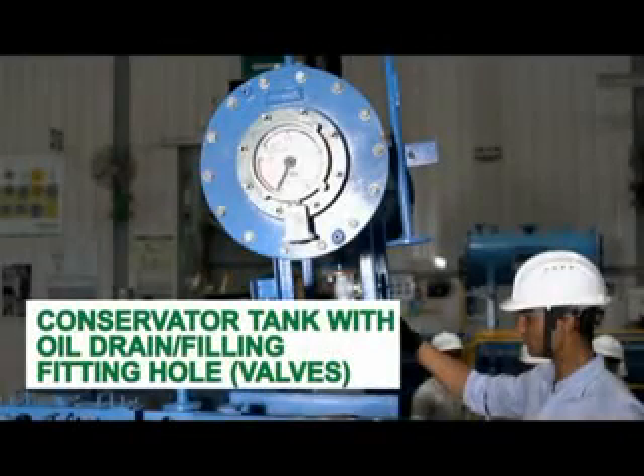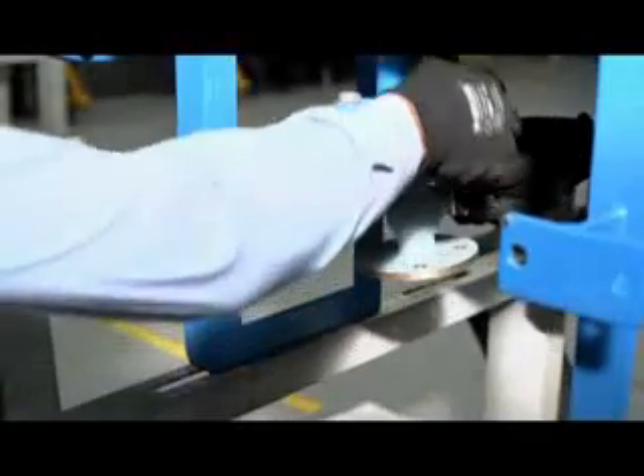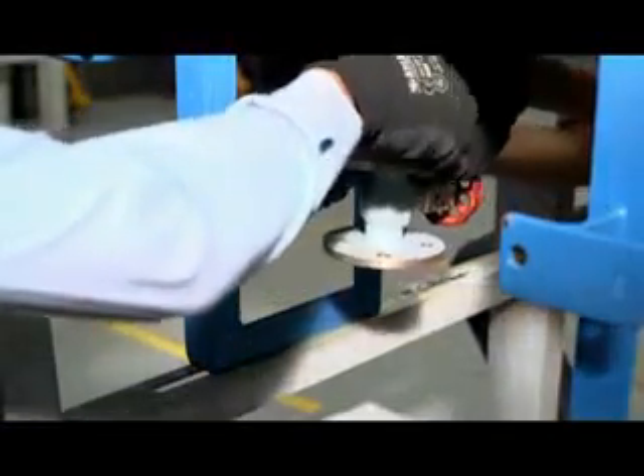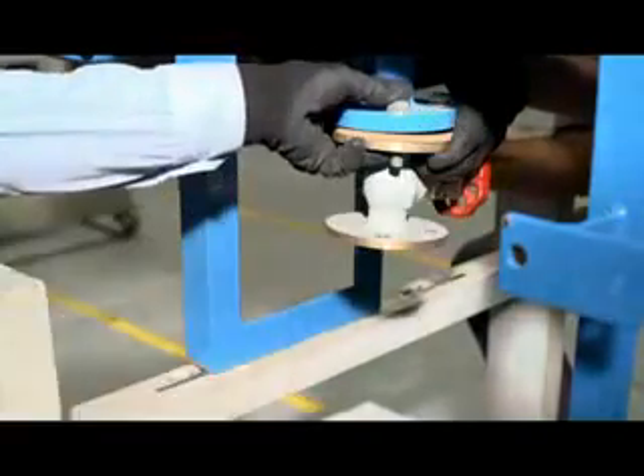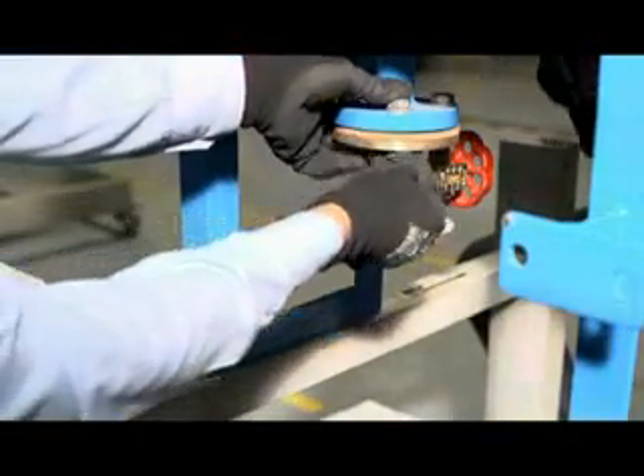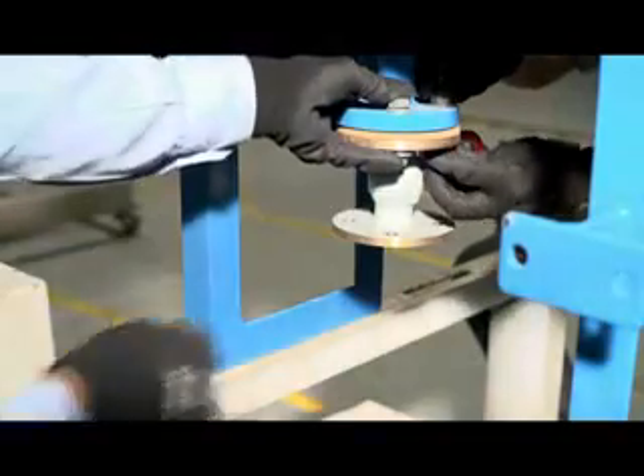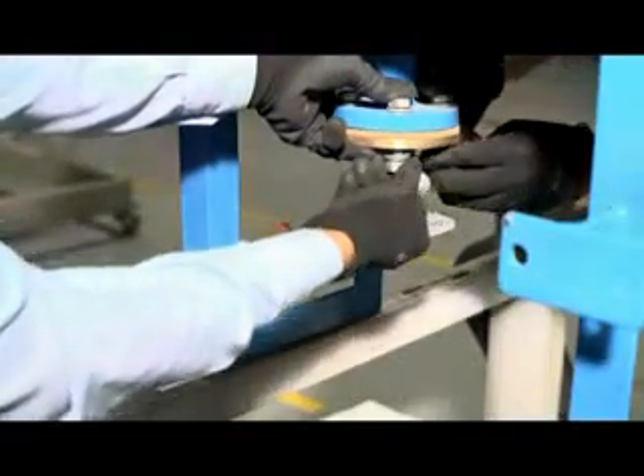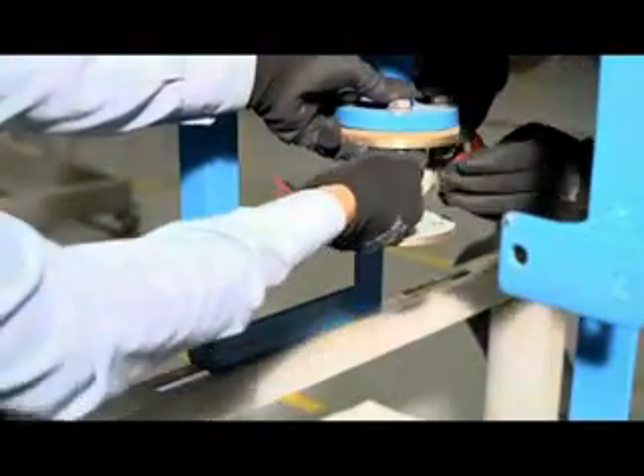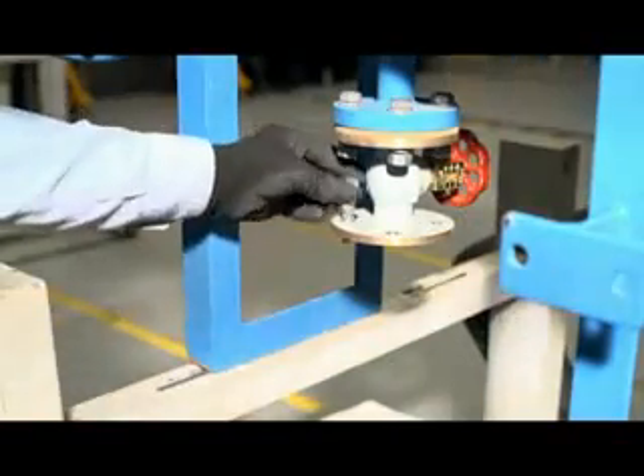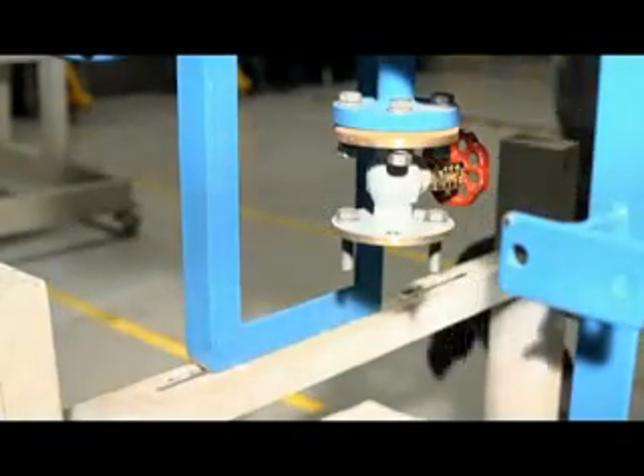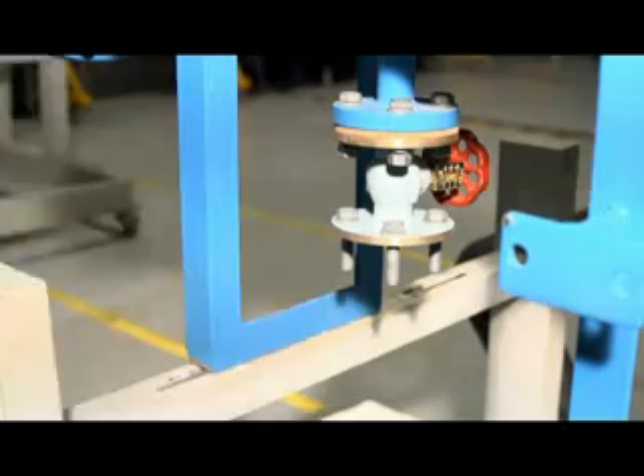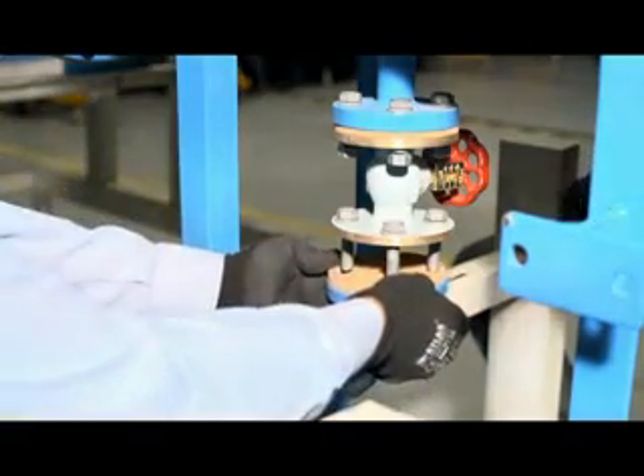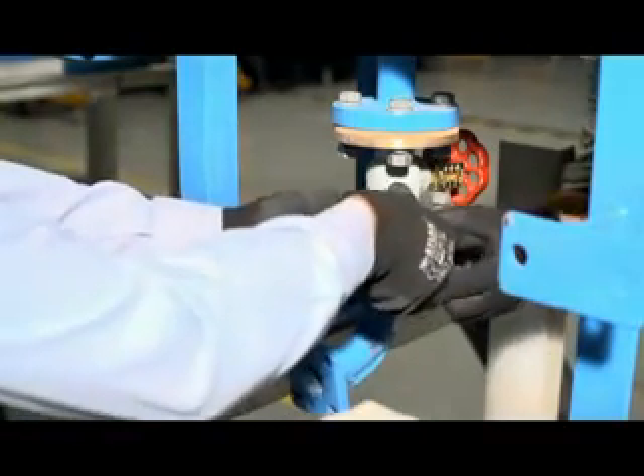Conservator tank with oil drain, filling, fitting hole, valves. This is a cylindrical tank mounted on a supporting structure on the roof of the transformer main tank. The main function of the conservator tank of a transformer is to provide adequate space for expansion of oil inside the transformer. When the transformer is loaded and when the ambient temperature rises, the volume of oil inside the transformer increases.